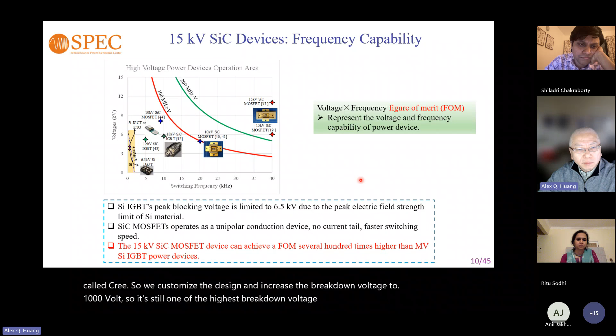The major takeaway for why we want this device is higher voltage, everybody understands that, but we also need to talk about frequency. Higher voltage and higher frequency is important for solid state transformers. It's not important for applications like HVDC or MMC, where you don't really need to switch at very high frequency. The reason is we have a galvanically isolated transformer, and the transformer size scales directly as voltage times frequency. So this number needs to be large to make the transformer smaller.